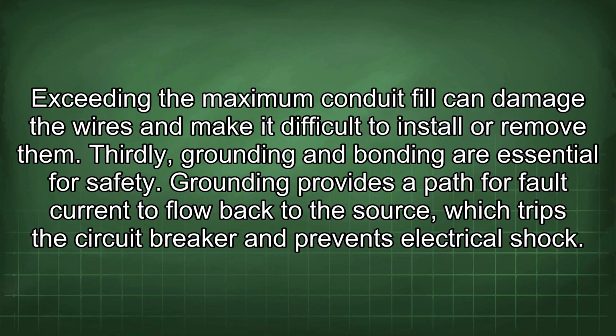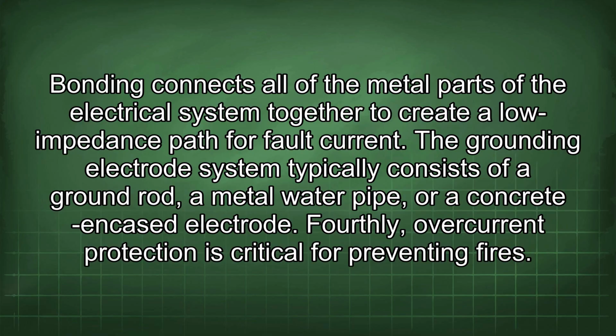Thirdly, grounding and bonding are essential for safety. Grounding provides a path for fault current to flow back to the source, which trips the circuit breaker and prevents electrical shock. Bonding connects all of the metal parts of the electrical system together to create a low impedance path for fault current. The grounding electrode system typically consists of a ground rod, a metal water pipe, or a concrete encased electrode.